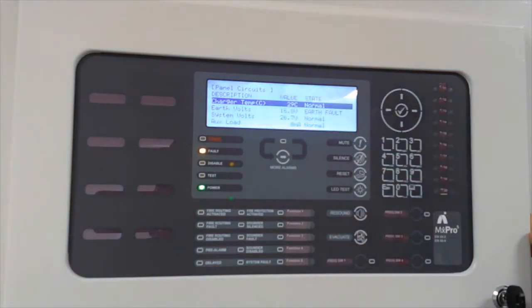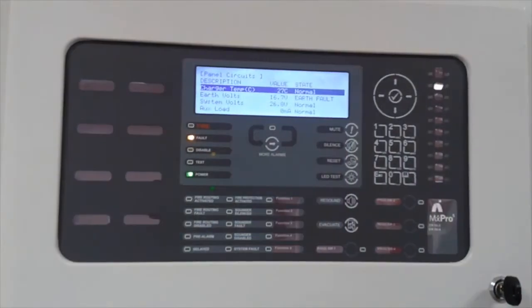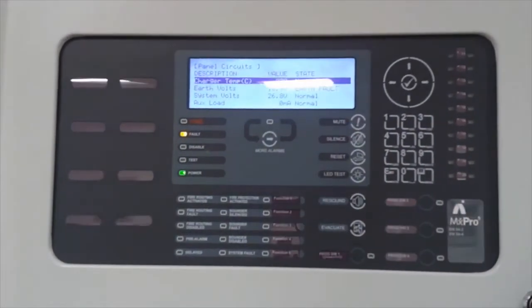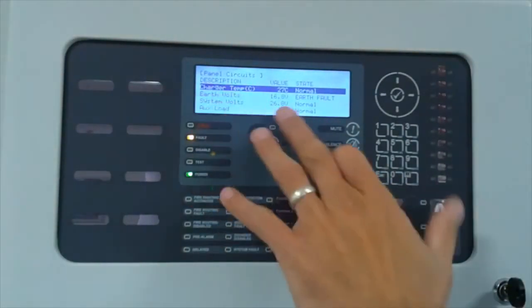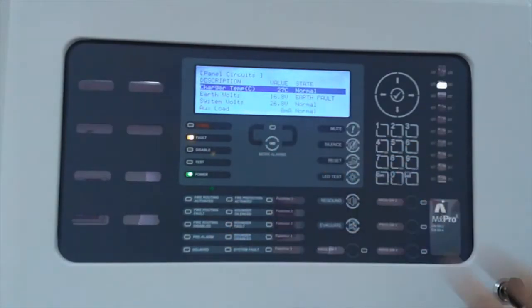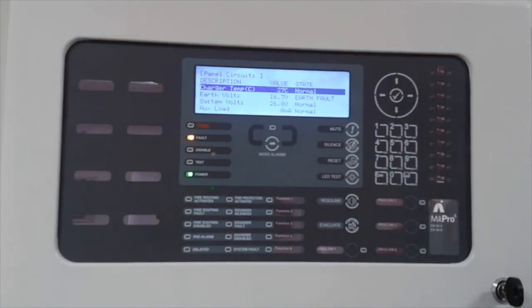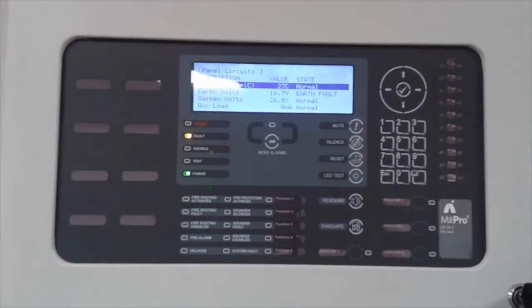So where do our earth faults come from? So 9 times out of 10, it is most common from your field wiring. When we look at the control panel, so if we open it up, we use this as a tool. So what we do is we remove the field wiring one at a time until we establish which circuit actually the earth fault has been induced on.